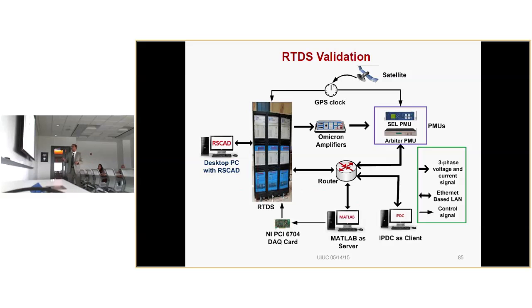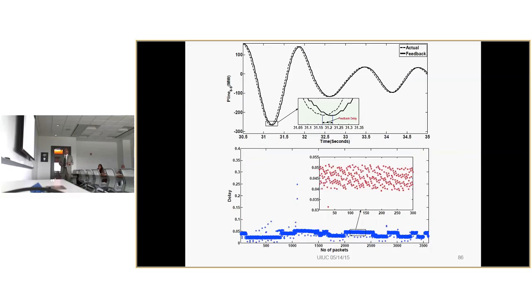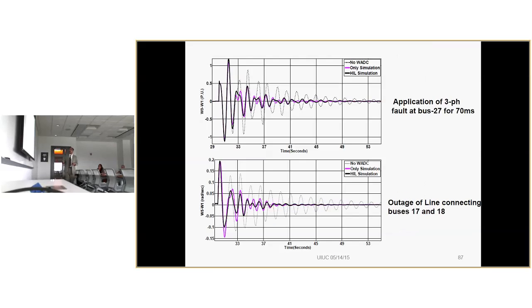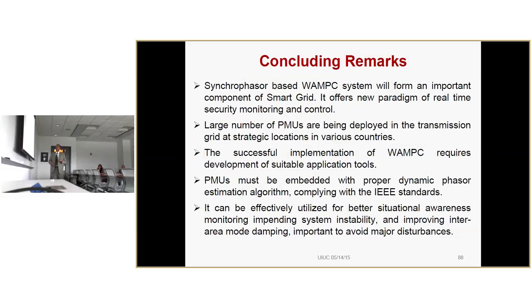Okay. So this was tested in our lab. And the actual and feedback signals were almost matching, with a slight difference. This is the random delay which was introduced. And this is the performance of our controller. So there is a slight difference between only simulation and hardware-in-the-loop simulation because of the different models used in MATLAB and RTDS. But if you don't use the WADC damping controller, then it gives a very poor response. So, just to conclude, I think I took slightly more time.